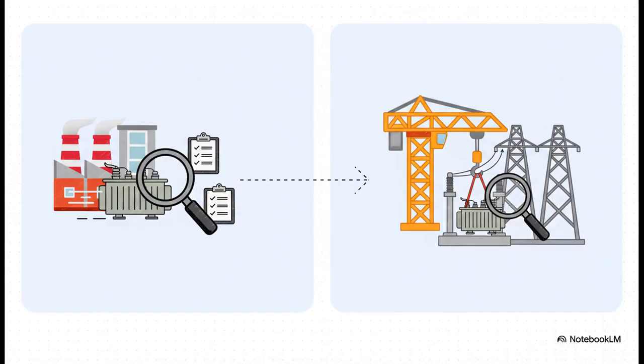This verification happens at two really important stages. First, there's the factory acceptance test, or FAT. That's done before the transformer even leaves the manufacturer to make sure it was built perfectly. Then, after it's been shipped and installed, it goes through a Site Acceptance Test, or SAT, to make 100% sure nothing got damaged along the way and that it's ready to be safely energized.